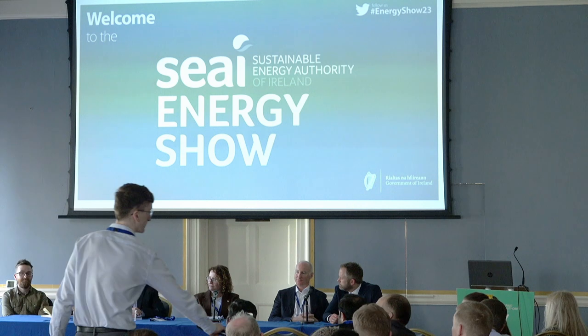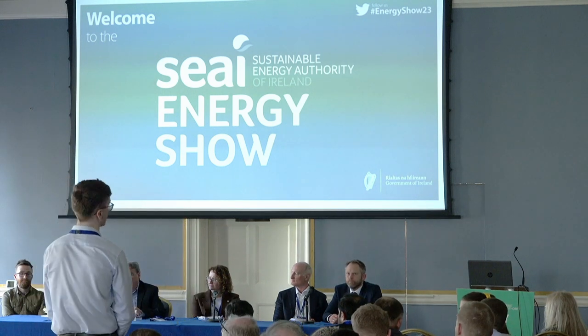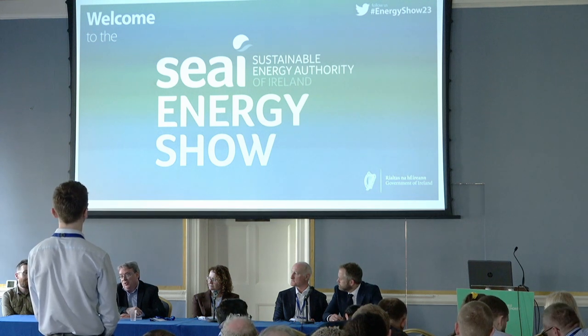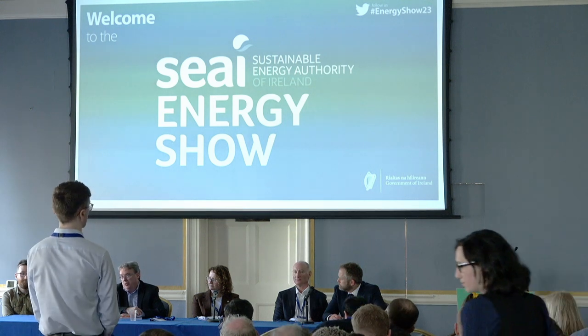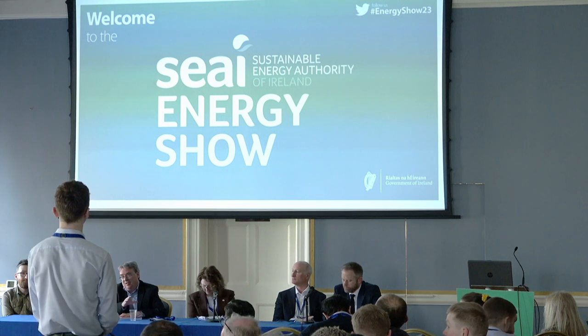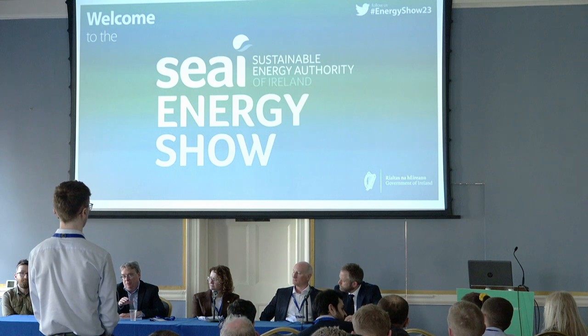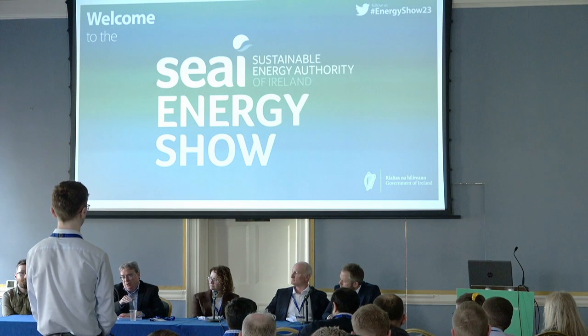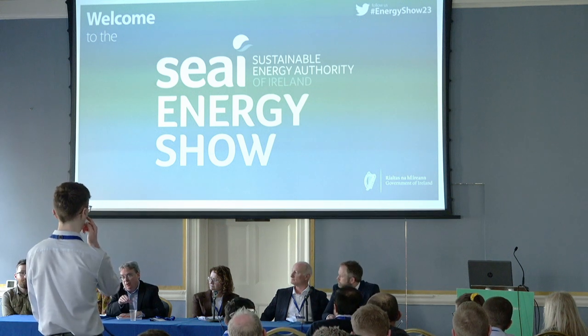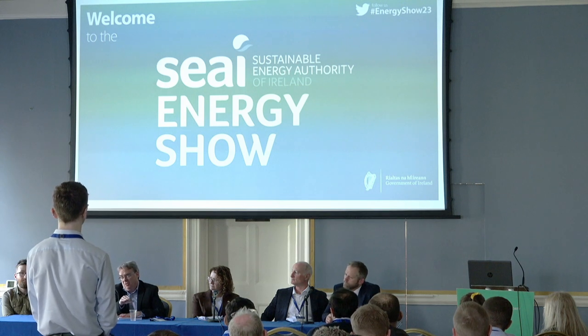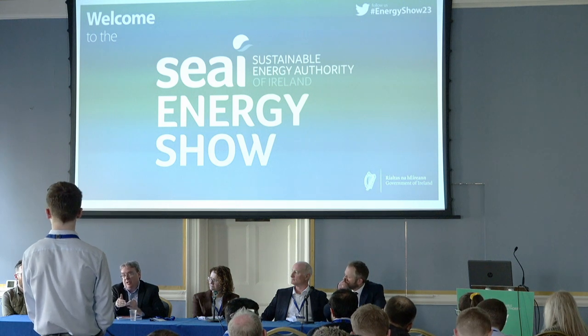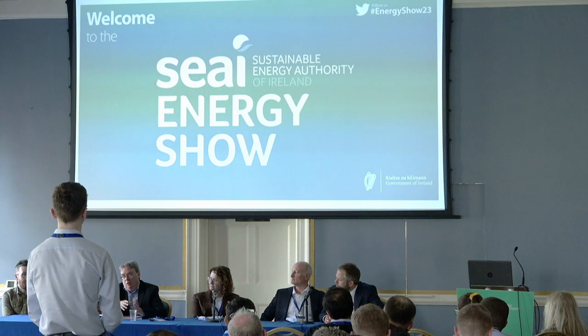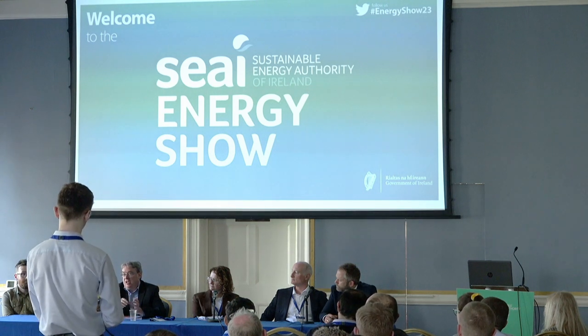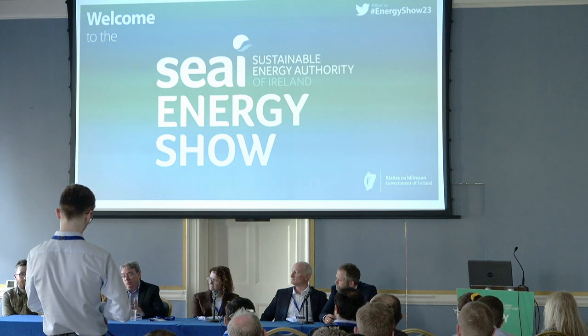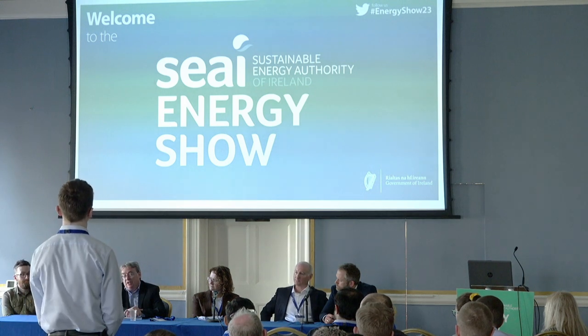Thanks very much. Well, there's a mix of solutions. Certainly in some building applications we're looking at, we are improving insulation, reducing air leakage, replacing glazing, and that's allowing us to operate at a lower water flow temperature from a heat pump. However, what's happening against that is heat pump technology is improving as well, and really the main improvement is allowing higher temperatures of operation. So there are CO2 heat pumps now that can operate at 80 degrees C, and in other cases we're using heat pumps at that temperature. In other cases, we're adopting a phased approach of replacing gas boilers, using a combination of heat pumps at lower temperatures mixed with boilers retained from before at higher temperatures, which allows us to maintain system operation. So again, it really depends on a project-by-project basis.